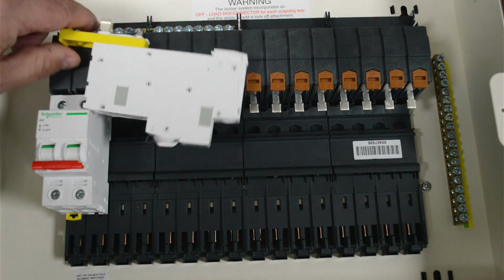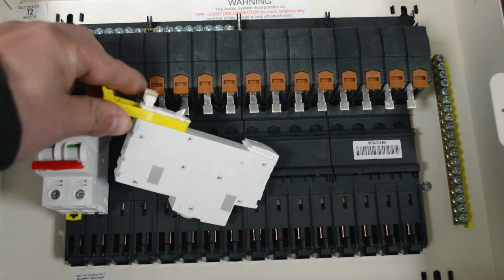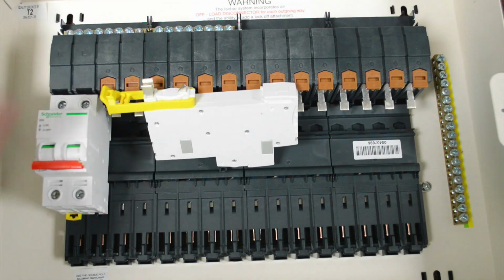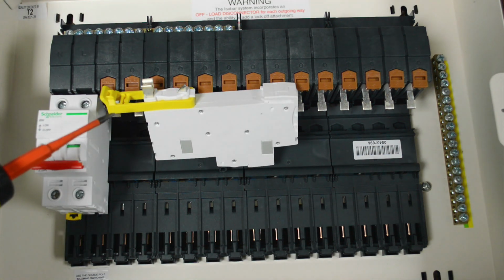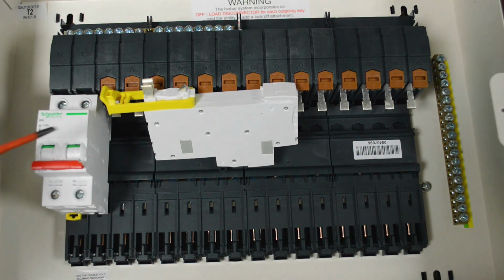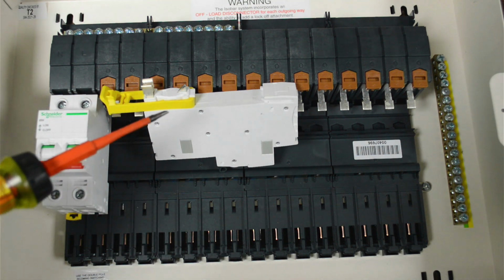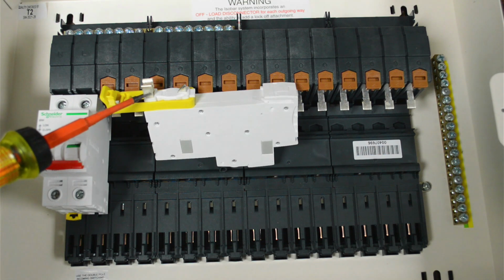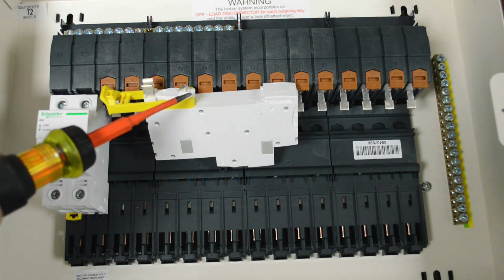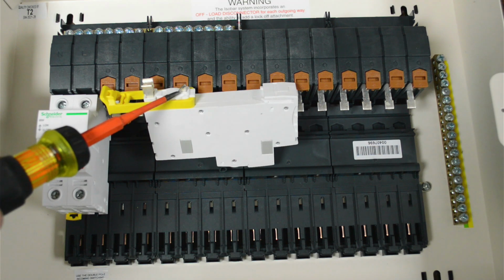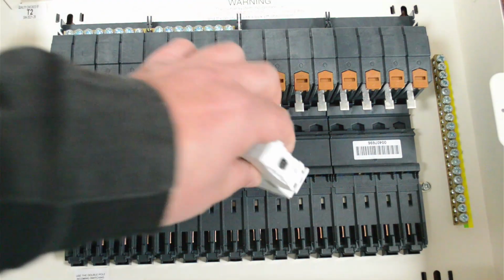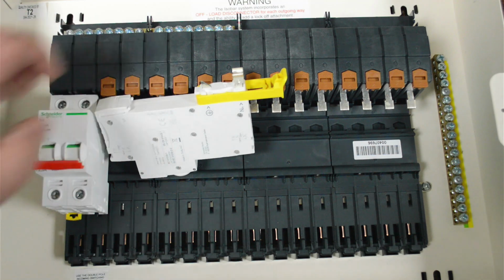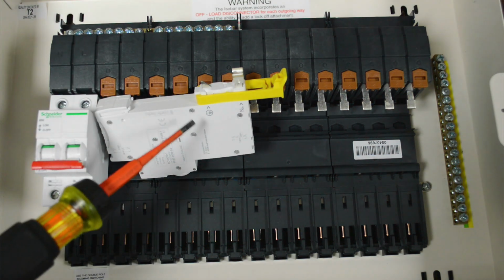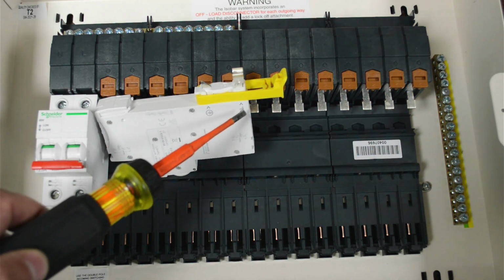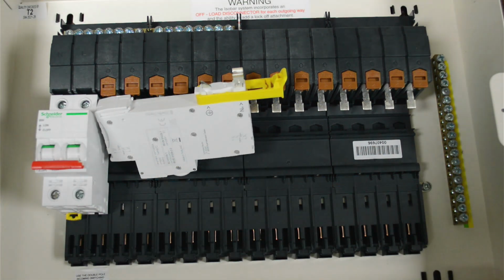so I will drop it into shot now. And if you see on the back of it, position it in a way that helps make sense. There's the yellow tab here, which is what you use to release the RCBO, and I'll show you that in a second. But if you look on the back there is the prongs, that's for the neutral connection, and then this little pin here, which is for the CPC/earth. If I spin it around, it actually shows those markings on the actual device itself, so you can see there the earth symbol, and then you've got your neutral symbol there as well.